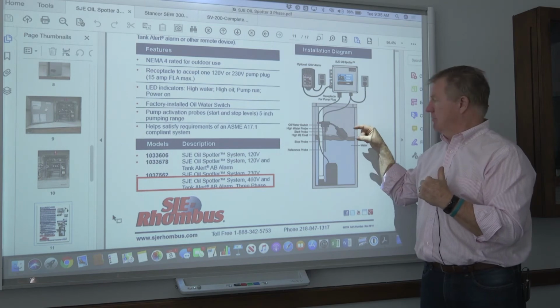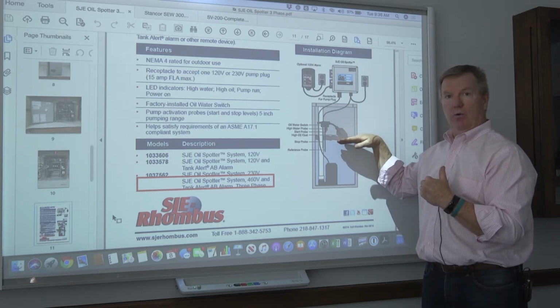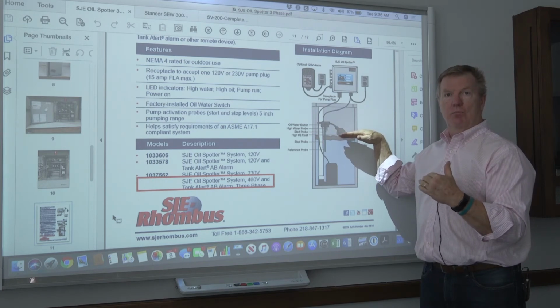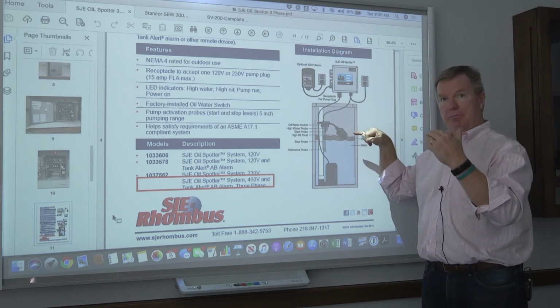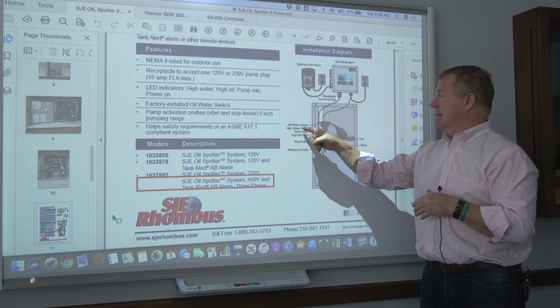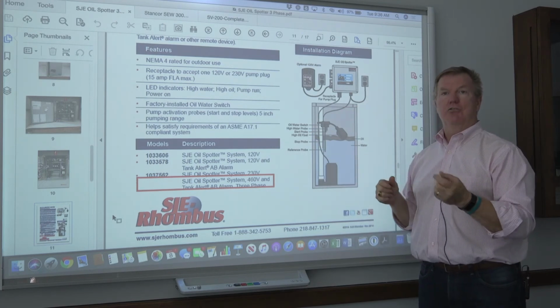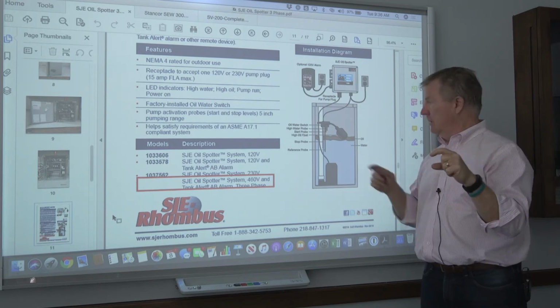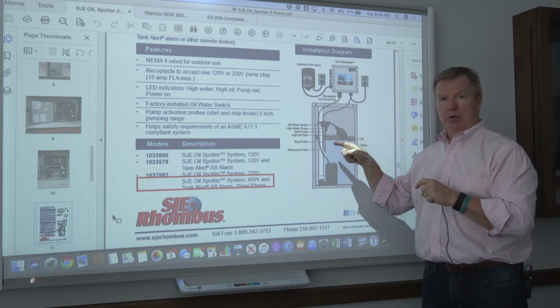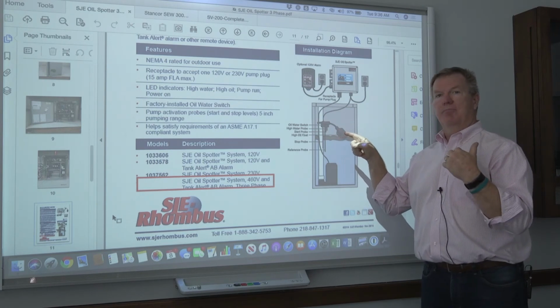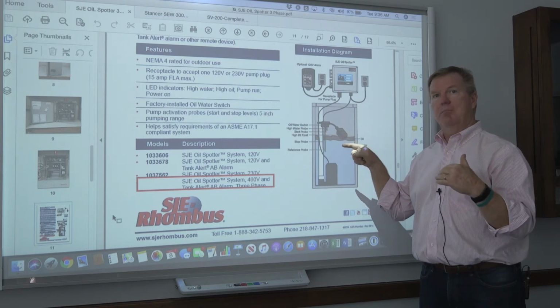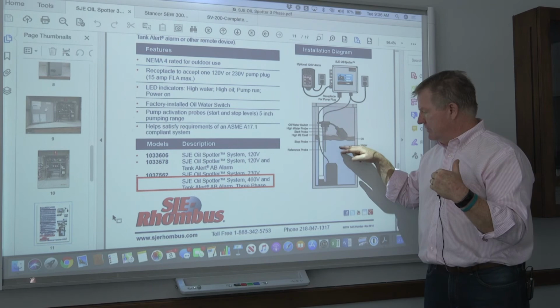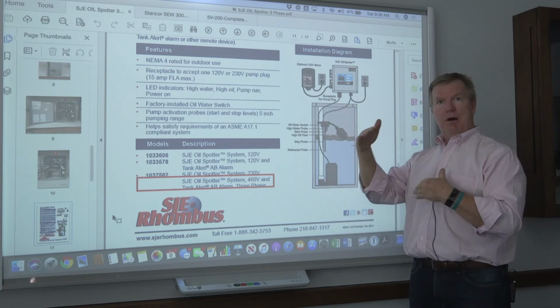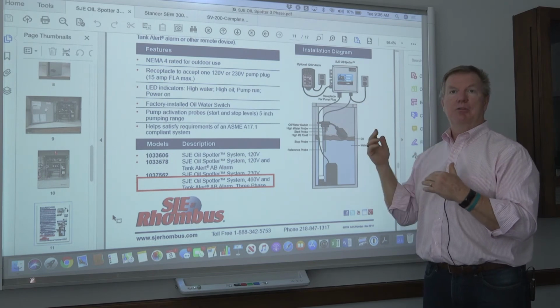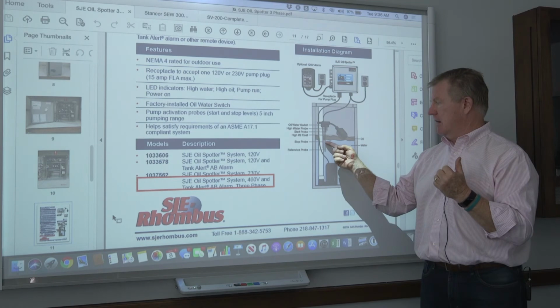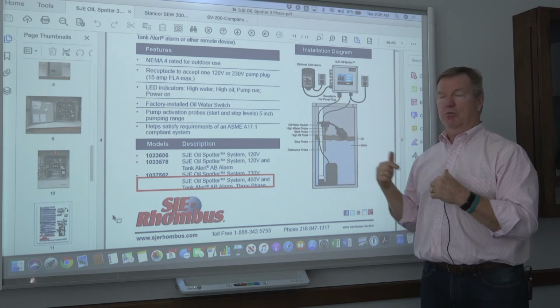top of the water, at some point when the water level is going up and approaching the start level for the pump, this float switch floating on top of the oil will actually activate the high oil level and tell you that there's an accumulation of oil on top of the water. Now the start and stop operation of the sump pump will continue to turn the pump on and off. It's just that it turns the pump off before this oil level moves down and gets pulled into the pump. So you'll still be pumping the water out of the sump, but the sump pump will typically, because of this stop probe location, turn the pump off before it starts to pull in oil.